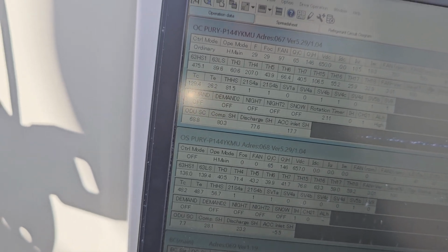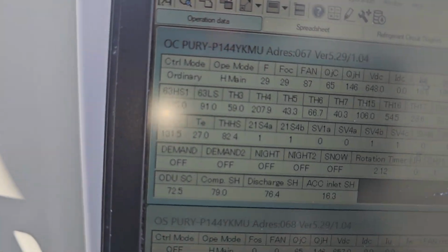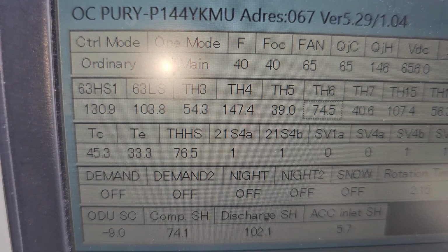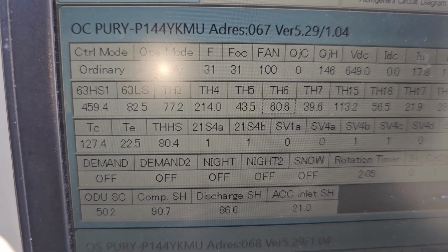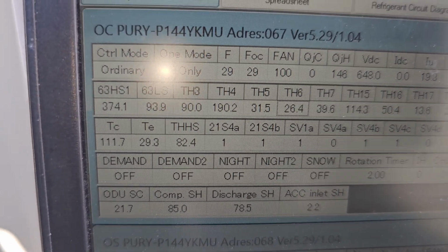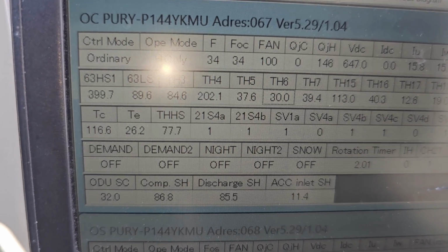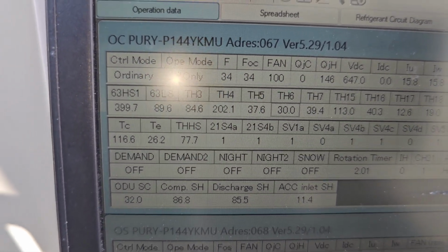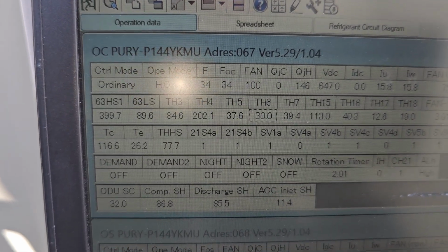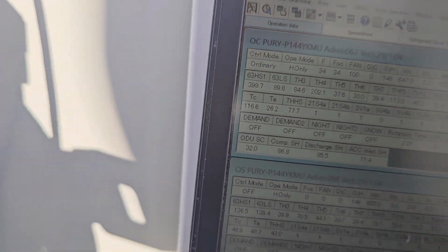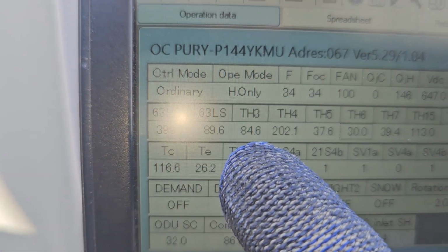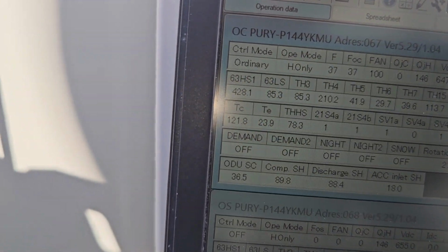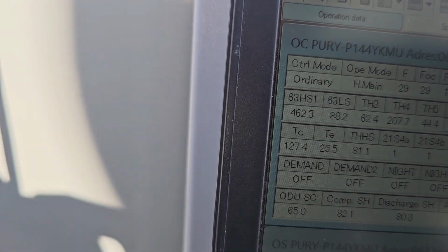So after watching it for quite some time more, and like I said, now if we cycle through, that looked pretty dang good. Our TC's 120. Our low side came up from negative to 26 degrees, right where I'd pretty much expect it. Now the only thing that was weird is our TH3, 84 degrees, and that side looks somewhat okay, but that wasn't the case the whole time.